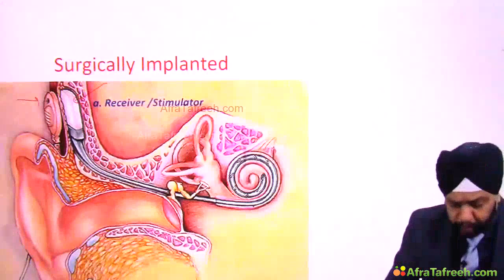So the receiver stimulator, it receives the EM waves. So remember, the transmitter over here was sending the electromagnetic waves, the EM waves. They cross the skin and then they are received by the receiver. So it's not just a receiver, it's a receiver and stimulator. So it receives the EM waves and it converts them back into electrical signal and it stimulates this electrode array. Okay, so when it stimulates the electrode array, now the electrode array goes inside the cochlea. So it is implanted in the scala tympani.